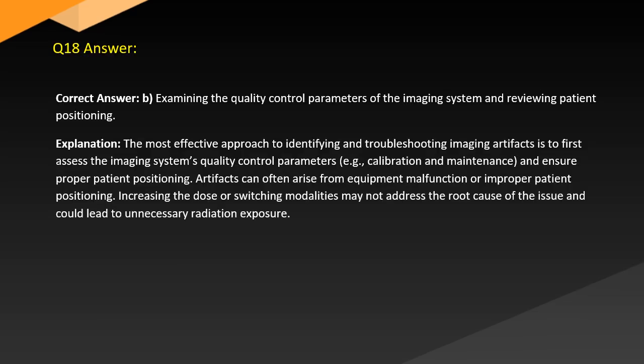Answer. Correct answer: B. Examining the quality control parameters of the imaging system and reviewing patient positioning. Explanation. The most effective approach to identifying and troubleshooting imaging artifacts is to first assess the imaging system's quality control parameters, e.g. calibration and maintenance, and ensure proper patient positioning. Artifacts can often arise from equipment malfunction or improper patient positioning. Increasing the dose or switching modalities may not address the root cause of the issue and could lead to unnecessary radiation exposure.